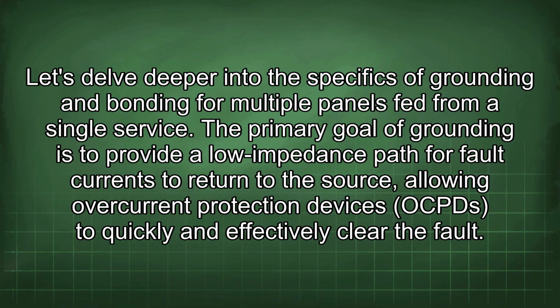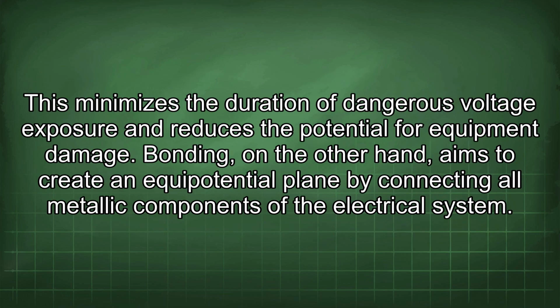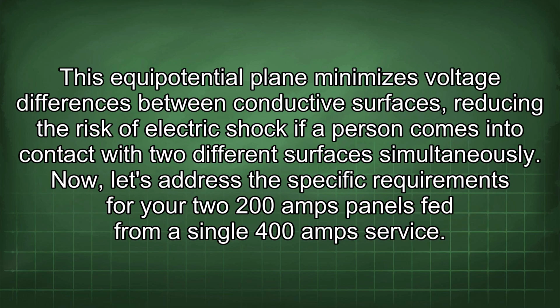The primary goal of grounding is to provide a low impedance path for fault currents to return to the source, allowing overcurrent protection devices to quickly and effectively clear the fault. This minimizes the duration of dangerous voltage exposure and reduces the potential for equipment damage. Bonding, on the other hand, aims to create an equipotential plane by connecting all metallic components of the electrical system. This equipotential plane minimizes voltage differences between conductive surfaces, reducing the risk of electric shock if a person comes into contact with two different surfaces simultaneously.